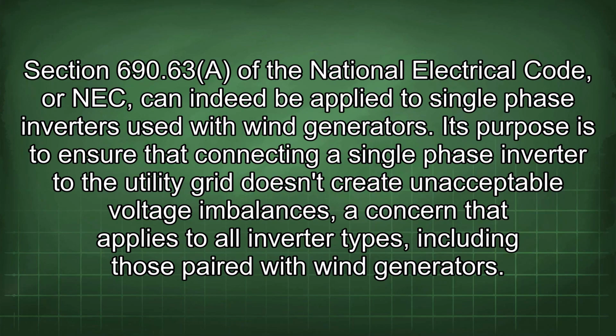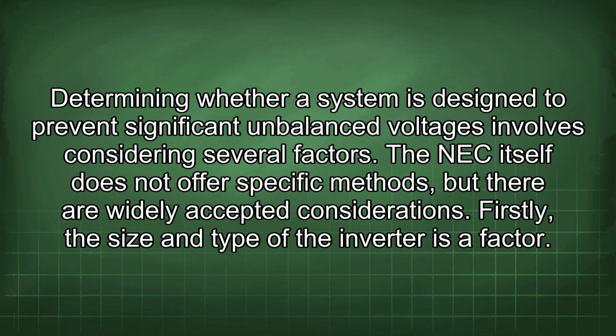690.63 of the National Electrical Code, or NEC, can indeed be applied to single-phase inverters used with wind generators. Its purpose is to ensure that connecting a single-phase inverter to the utility grid doesn't create unacceptable voltage imbalances, a concern that applies to all inverter types, including those paired with wind generators. Determining whether a system is designed to prevent significant unbalanced voltages involves considering several factors.